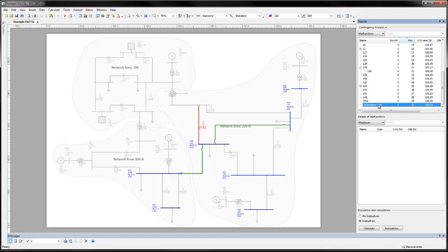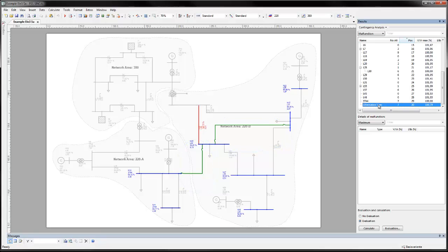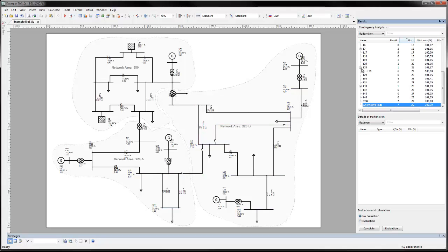In the Alternative Lines scenario, by reconnecting the two lines, shown here in green, line 30 no longer becomes overloaded and no element in the network are without supply. Contingency scenarios can be applied for the testing and design of network remedial measures.